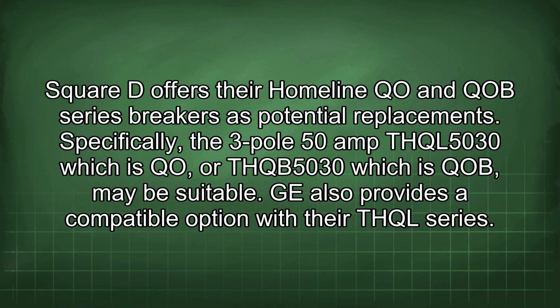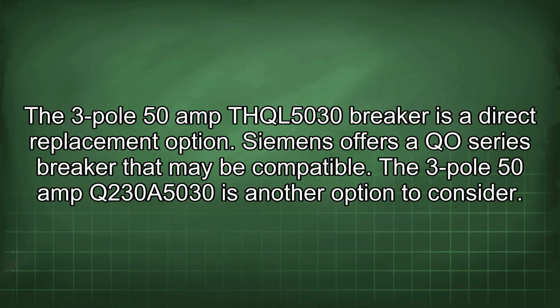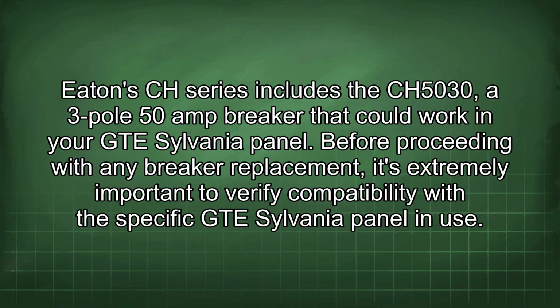GE also provides a compatible option with their THQL series. The 3-pole 50 amp THQL 5030 breaker is a direct replacement option. Siemens offers a QO series breaker that may be compatible. The 3-pole 50 amp Q230 5030 is another option to consider. Eaton's CH series includes the CH5030, a 3-pole 50 amp breaker that could work in your GTE Sylvania panel.